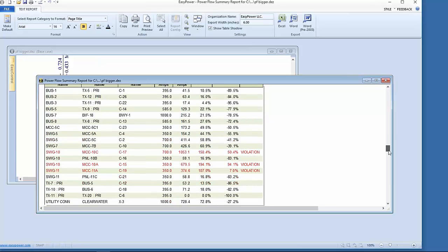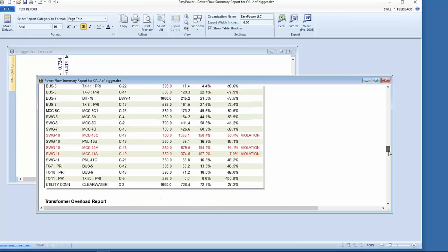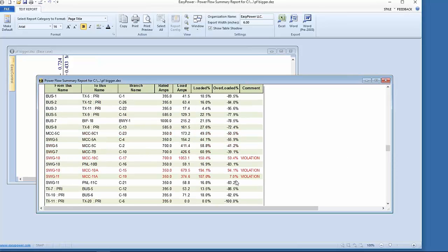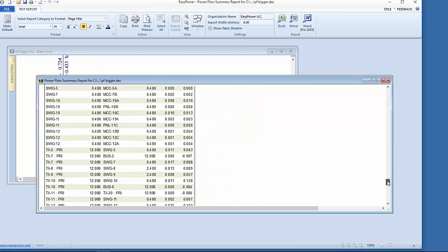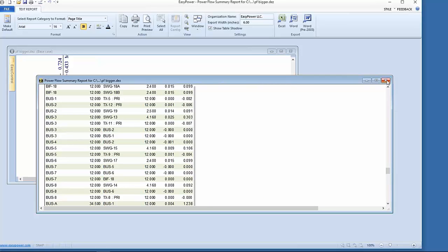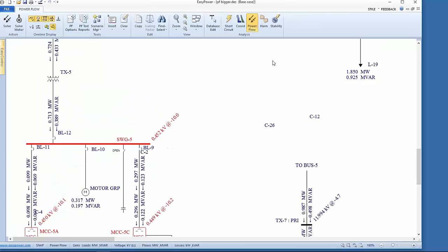And as we walk through the plant and update those settings, we will get more accurate results in terms of the alignment of these outputs with the readings we take in the plant, which is another way to make our settings, is to measure the current and the voltage, and then identify the source of any of those loads, so that what we're really tracing are the unexpected, if you will, losses, because they will identify the areas of opportunity.